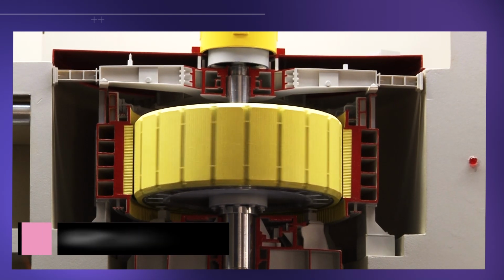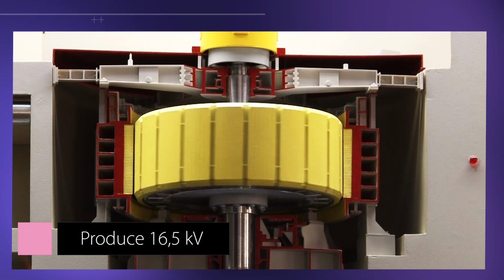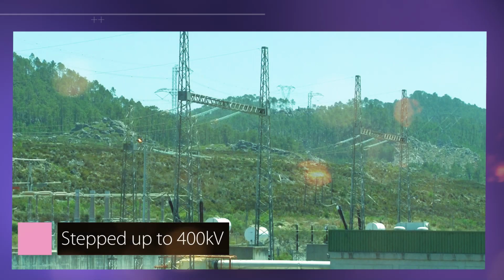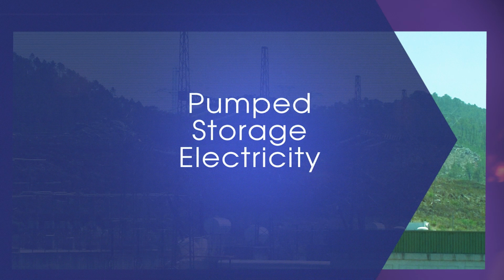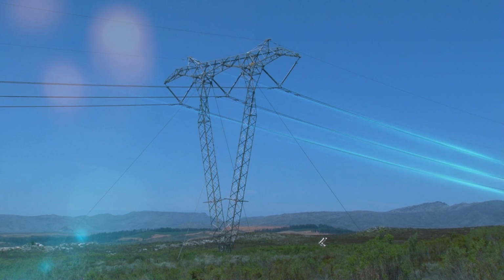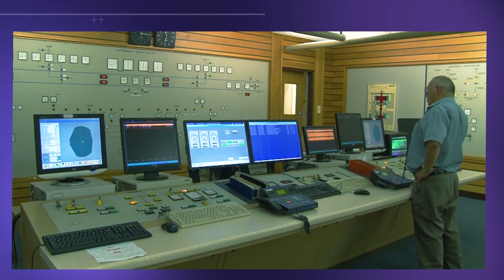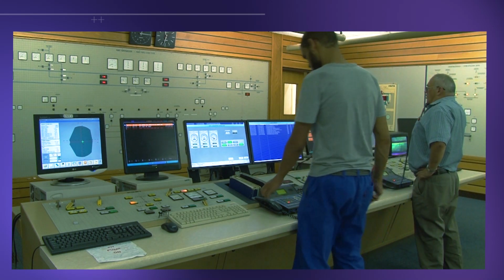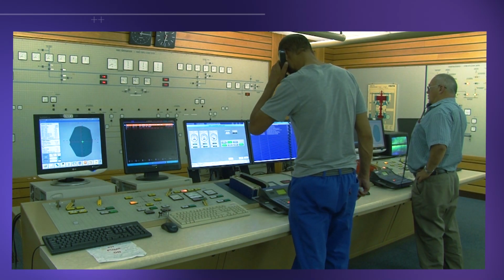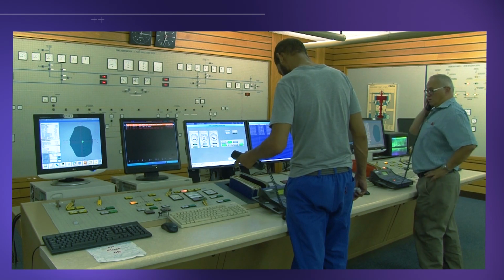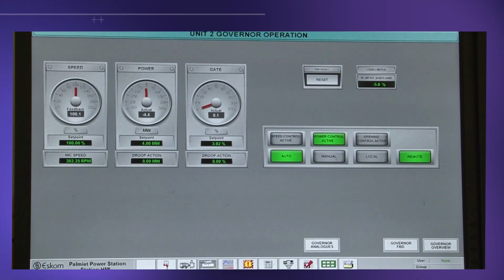The generator motors produce 16.5 kilovolts, which is then stepped up to 400 kilovolts by generator transformers installed in the high voltage yard just outside the station. 2 400 kilovolt lines connect into the national grid. Palmiet is manned 24 hours a day and receives its instructions directly from the National Control Room in Johannesburg. National Control monitors the electricity supply and demand in South Africa.